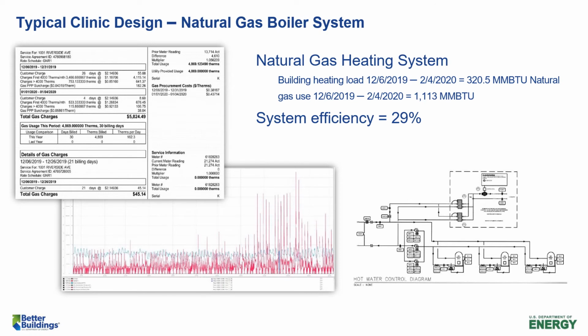I think this is another key moving forward in healthcare. I was a design engineer for a decade and some change, and I did designs on hundreds of buildings. I used the standard design tools, Trace 700, DOE2, Energy Plus. But never once in my career did I collect the data to look at the heating load in the coldest week of winter. Never once did I collect the data to look at the cooling load in the hottest month of summer. Never once did I validate the boiler plant efficiency or cooling plant efficiency. I designed hundreds of systems and I never did validation.